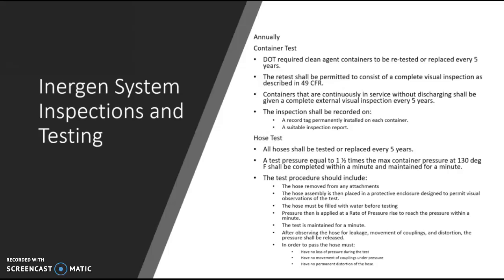DOT requires clean agent containers to be retested or replaced every 5 years. It requires a complete visual inspection, and it's described in 49 CFR. Containers that are continuously in service without discharge shall be given an external inspection every 5 years. Inspection shall be recorded on the tag and a suitable inspection report. Hoses should be tested every 5 years or replaced.